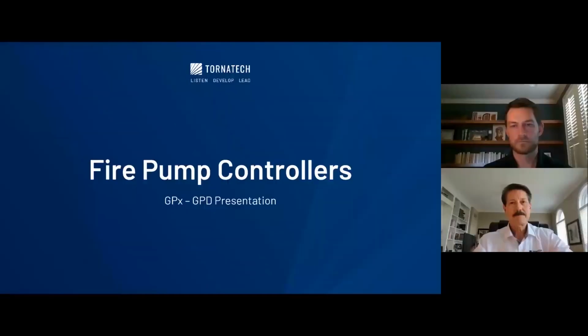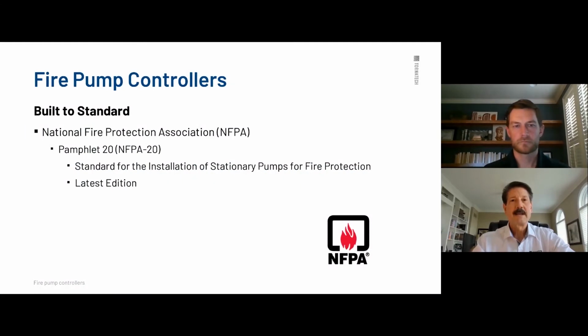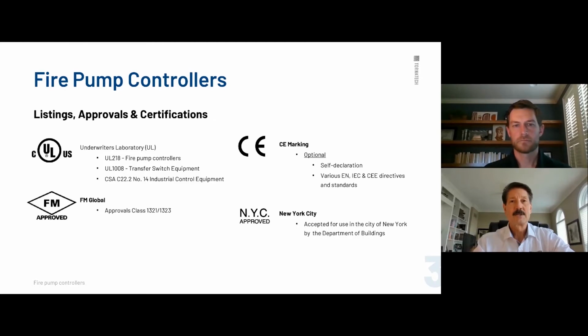Good. Well, let's get started. Fire pump controllers, GPx electric, GPD diesel. NFPA 20, everyone's heard of NFPA 20, National Fire Protection Association. Well, we as a manufacturer have guidelines that we must follow when we build a fire pump controller, and NFPA 20 is that guideline. In addition, we need a UL listing and an FM approval before we can ship any fire pump controller out the door in North America.